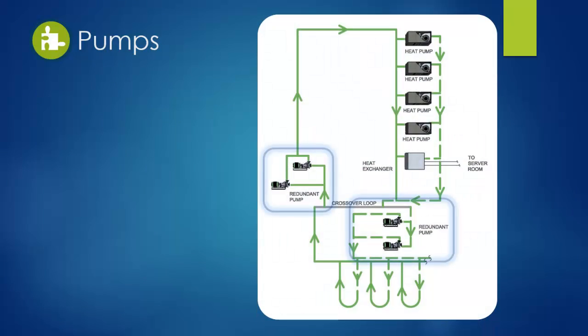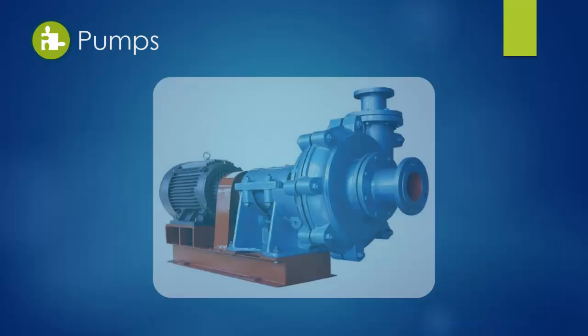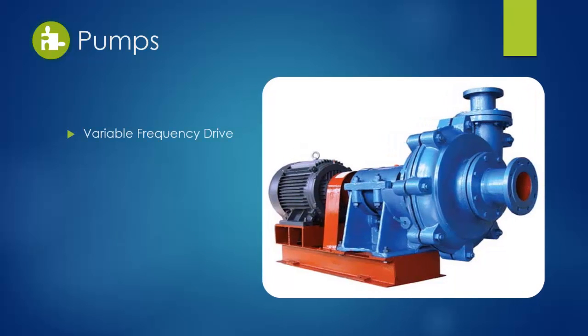To transfer the water from the boreholes to the space, 2 variable frequency drive pumps set up in parallel are used. The 2 pumps in parallel allow for redundancy if a pump were to go down. The variable frequency drive allows the pump speed to change based on the load to save energy.